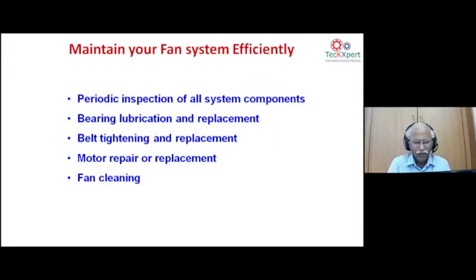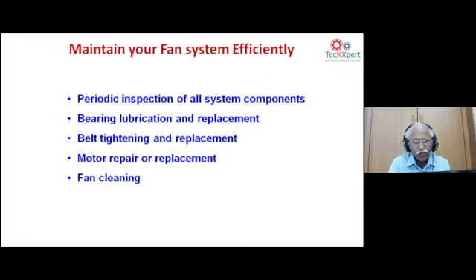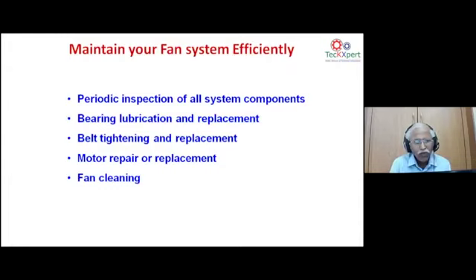Q (Devraj Kumar): What is the minimum distance to give at the fan outlet before a bend to avoid back pressure? A: On the delivery side, minimum three diameters; on the suction side, around two diameters — per BEE guidelines and OEM specifications. On the delivery side, install a velocity recovery ring or discharge tube cone; on the suction side, a bell-mouth inlet ensures air enters the fan in a streamlined manner.